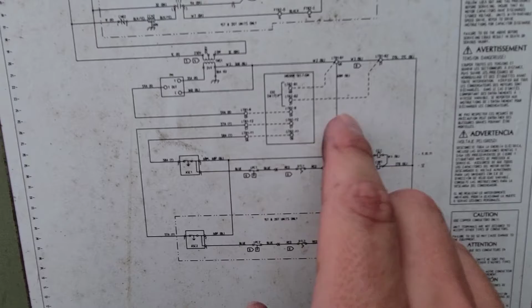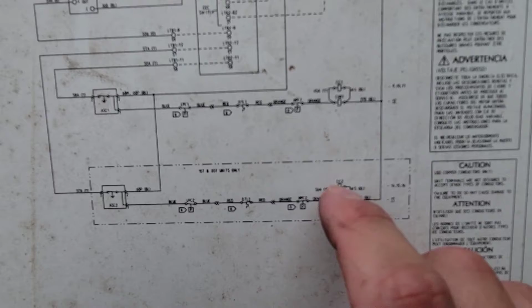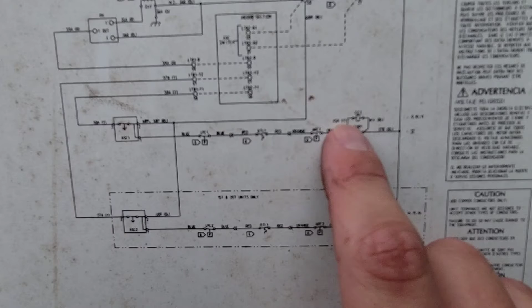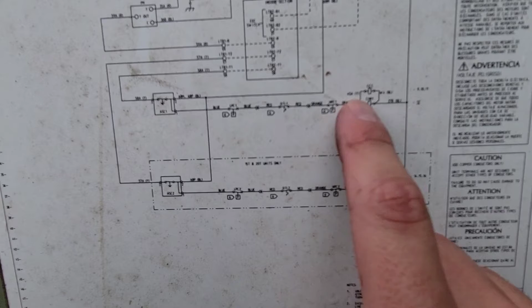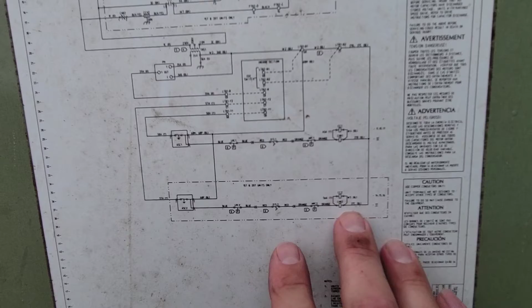go down here, the 24 volt section, where's our control voltage, you'll see I've got compressor number 1, CC1 and CC2. I've got a yellow and a blue wire that goes to the coil of the contactor. I took the yellow wire off of the coil of compressor number 2 down here, okay? This is compressor number 1, compressor number 2. So I took the coil wire off. That way you're no longer energizing that contactor. And then I also took the high voltage wires off.